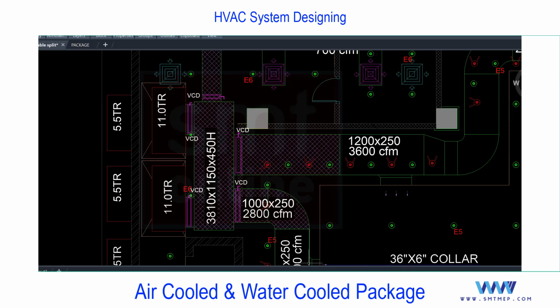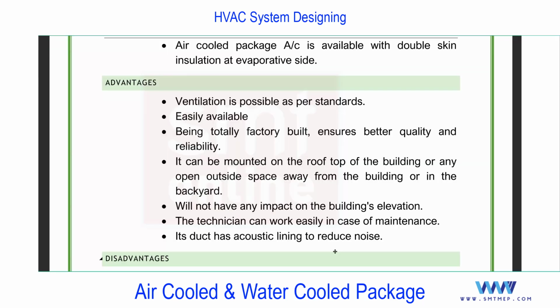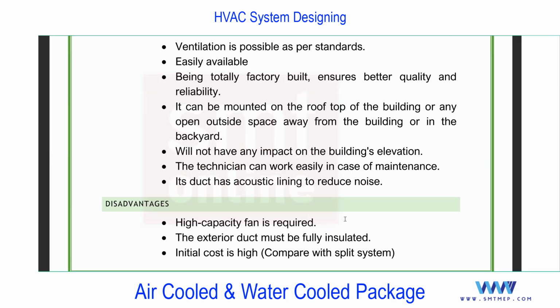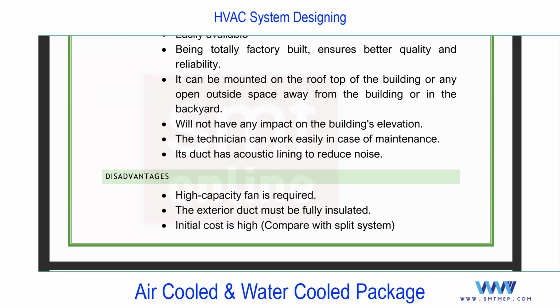Because the fan motor is the higher capacity, na? Because the fan motor is used to supply the air to the last air terminal. Okay. Next, if you talk about disadvantage, you see capacity of fan should be higher because we are placing the unit away from the conditioned space. From that point, we are interested to supply the air to the last air terminal. Okay, so the fan capacity comparing with the ductable split.